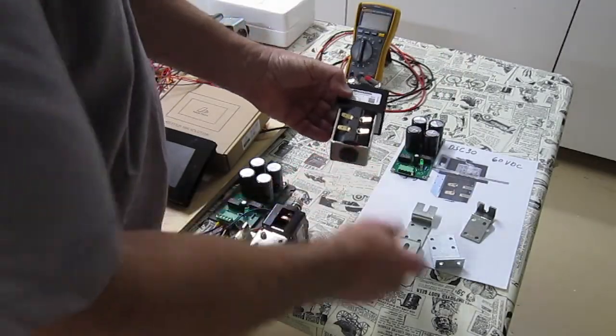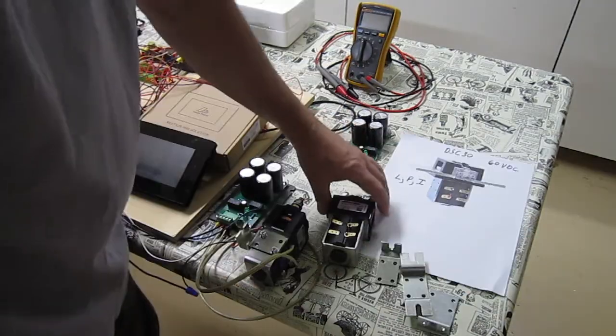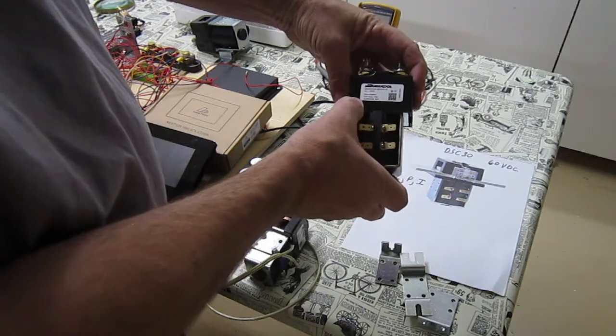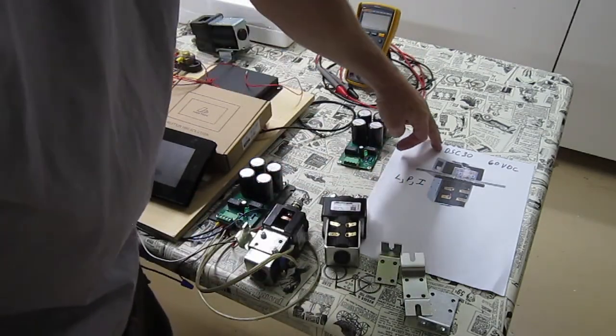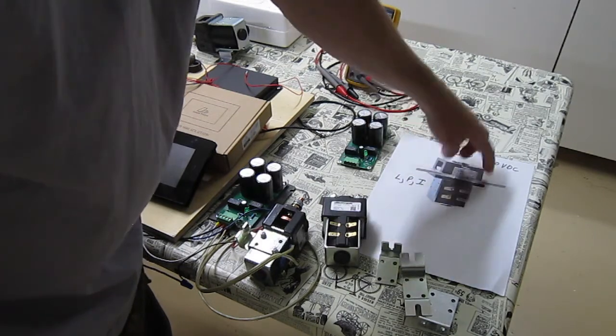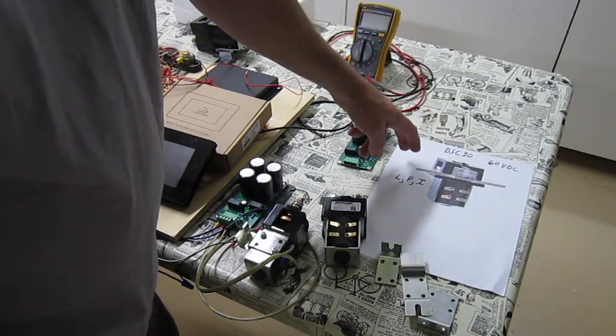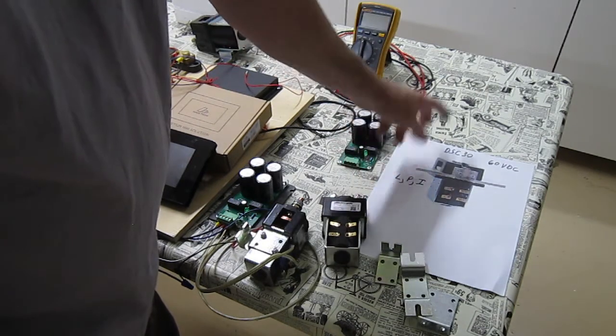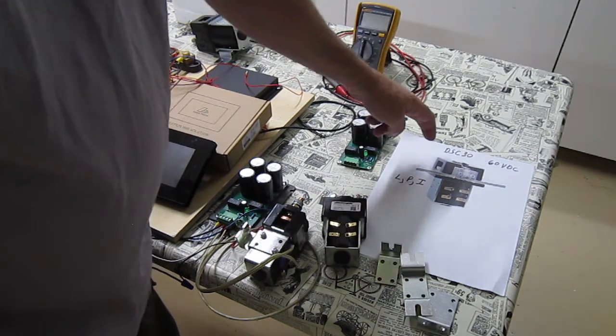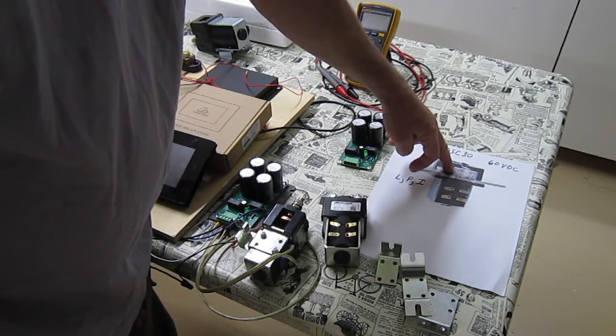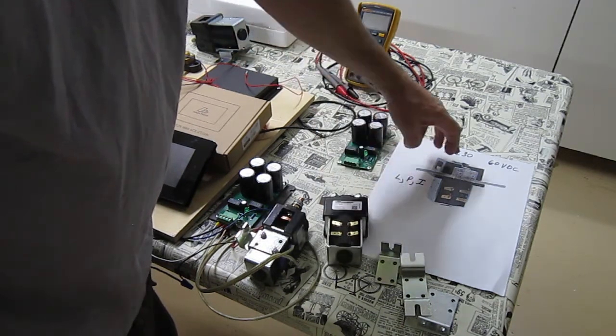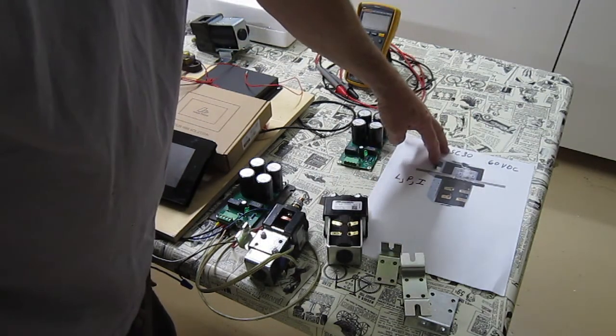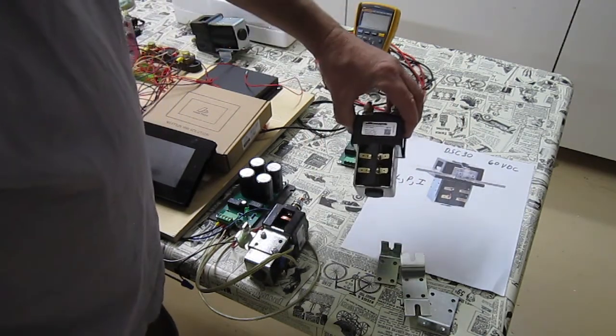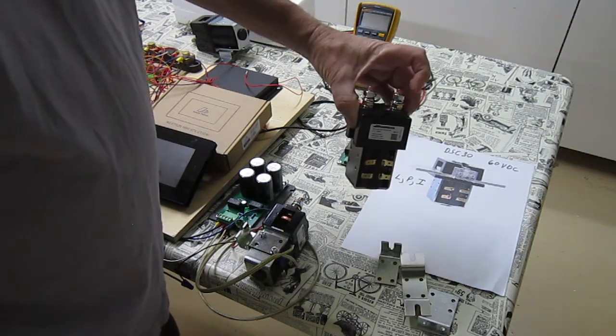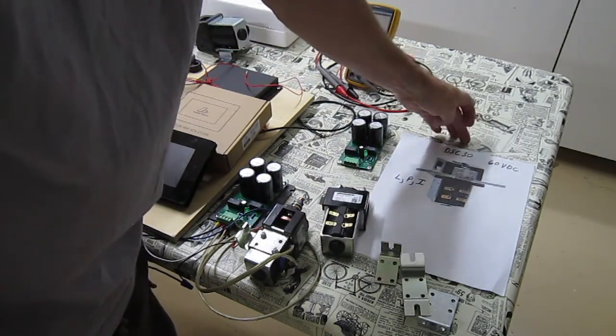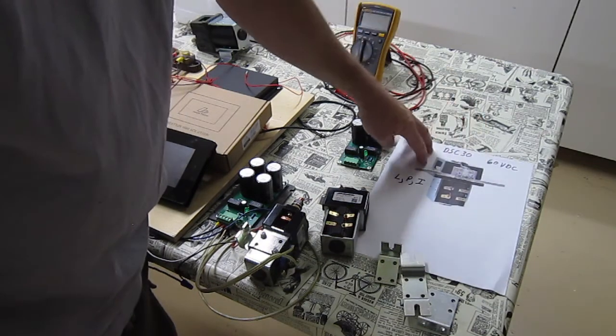When I ordered this product, there's actually 2 different models. This is their DSC30M, and they do have a DSC30. It has bus bars with 2 holes in it, which I thought was a nice feature in case you wanted to gang a couple batteries together in one spot and not have to purchase a separate bus bar. This is shown with auxiliary contacts, which I did not order. It has a lower voltage rating because it doesn't have magnetic arc blowout. This is rated up to 120 volts DC, the one with the 8mm studs. This one does not, so it's only rated at 60 volts DC, but it's still a 300 amp contactor.